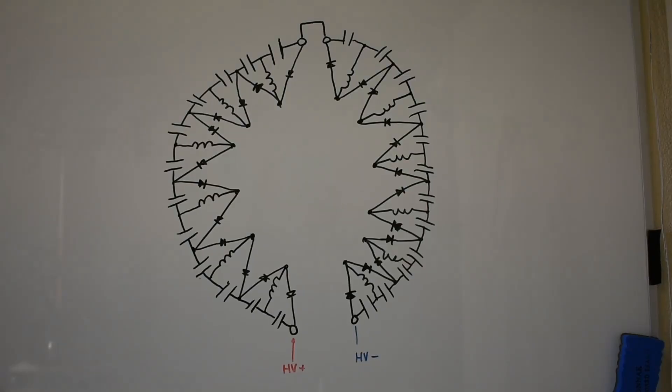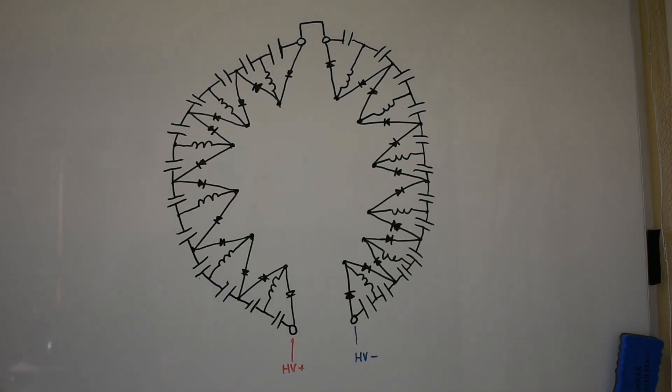This is the diagram of the circuit for that X-ray transformer. I've given the diagram exactly as it's laid out on the printed circuit board in this circle shape for simplification. You can see on the outside are all the capacitors, and I've illustrated these are the windings of each part of the transformer. So we have, I think it's 12 separate windings in total, or 12 secondaries on that transformer. Each one is connected to diodes and capacitors for the charge circuit. And the capacitors are all in series right round. They are when this link is in. This is now the link, which was the grounding point, which I've now put in place. And that gives us a plus high voltage and a minus high voltage out of the transformer.